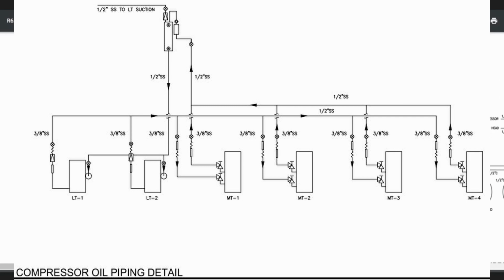This plant's been running for 2 years, and it took us a little while to balance the oil out and getting it out of the evaporators. And it turned out it was really an easy process once we figured it out. On the medium temp, at night, we shut off one. There's 4 plate heat exchangers on the liquid overfeed rack. And we turn one off and let it sit for about 10 minutes. And then we open, there's a drain line right at the bottom of the evaporator, or the outlet of the expansion valve and the inlet of the plate heat exchanger.